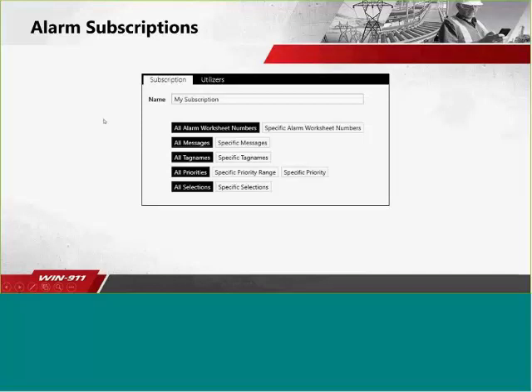Here is a screenshot of what an alarm subscription looks like within the WIN911 product. These are the different properties that we can filter on. The first one would be an alarm worksheet number or a group number. On the right, you can see from the PC demo, we have 3 different alarm sheets or worksheets or groups, whatever you want to call them. And we can filter on those numbers. So I can say, if an alarm is in the first group, then I want just those alarms. Or if it's in the second group, I just want those alarms, or the third. So I can create a subscription for each one of those.